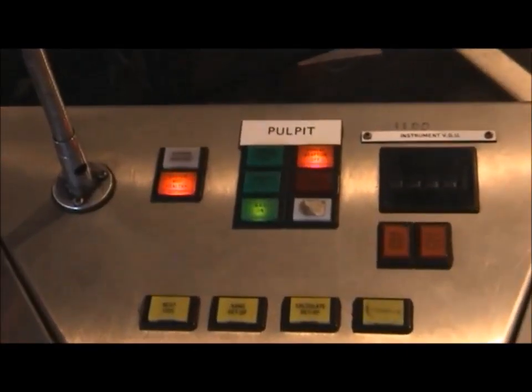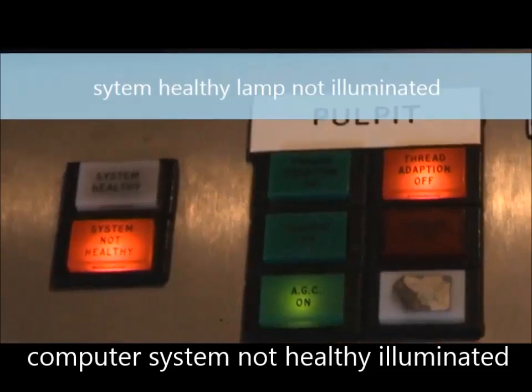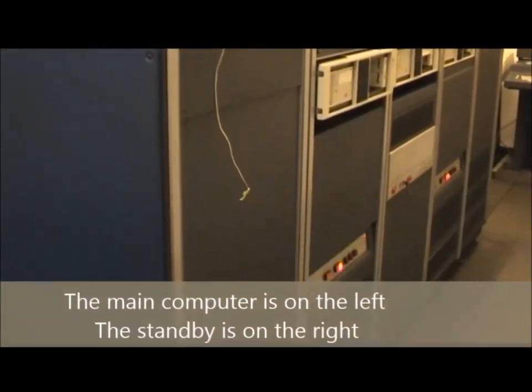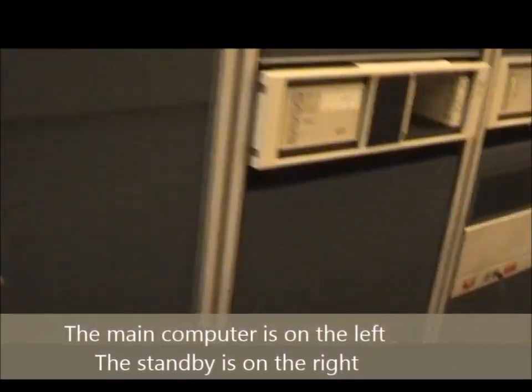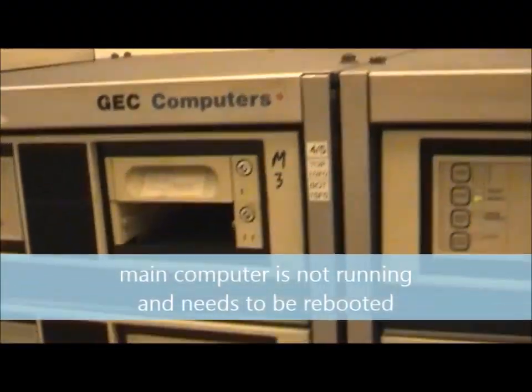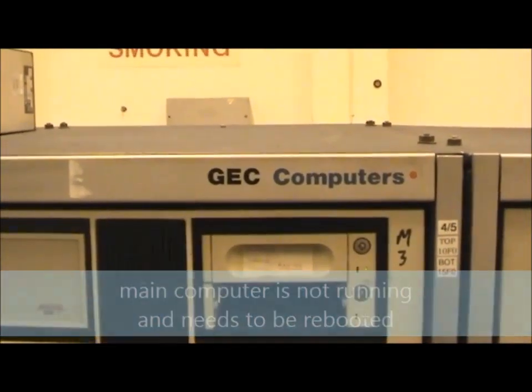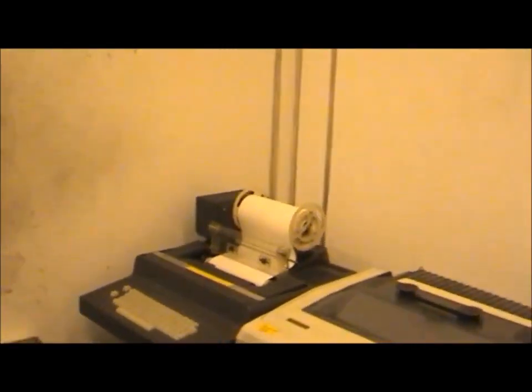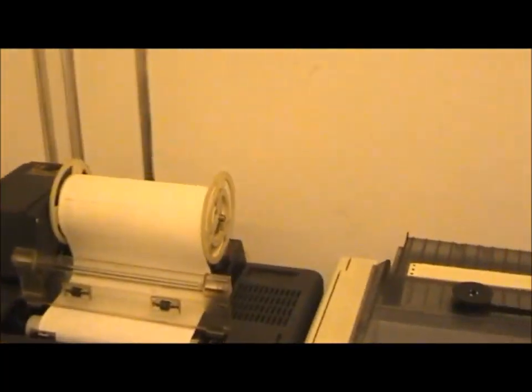Okay. The indication on the desk tells me that there's a problem. We haven't got system healthy. So I need to check the main computer. We have the main computer, standby computer. The main computer is not running. It's where the system disk drive is located in the switch extension unit. So I'll have to reboot the computer using the console.